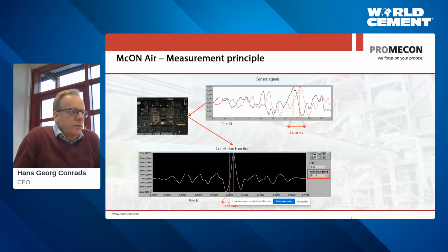It is also vastly different from any type of advanced measurement, such as ultrasonic or thermal anemometers. What we do here is we look at the direct pattern over time, we digitize, and we measure the time of flight directly by the cross-correlation calculation. And the big advantage of this measurement is that it is only dependent on time. There's no other variable in this equation except time.